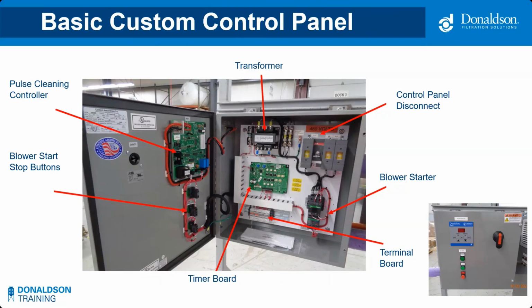So the main feature of this entire control panel is the Donaldson Delta P Plus controller, which was jointly developed as a simple printed circuit board device that monitors and controls the differential pressure in a dust collector, ensuring that the filters are cleaned effectively. It measures the pressure drop across the filters and initiates those cleaning cycles based on the user-defined high and low pressure set points. This helps maintain the optimal filter performance, extends the life, reduces the downtime, and increases efficiency. I'll toss it back to you, Asa.